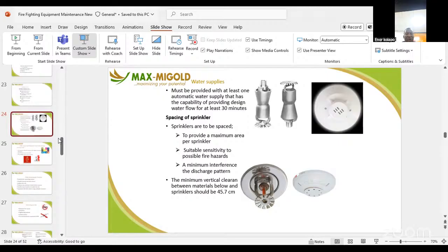capability, which then comes as a function of the water storage tank, function of your pump flow rate, function of the capability for the tanks to be refilled when it is working, and of course, function of the hazards available in the workplace. So the way we're going to design for an oil and gas facility or a tank that stores combustible liquid is different from how we're going to design a library, a place with maybe solid fuel.